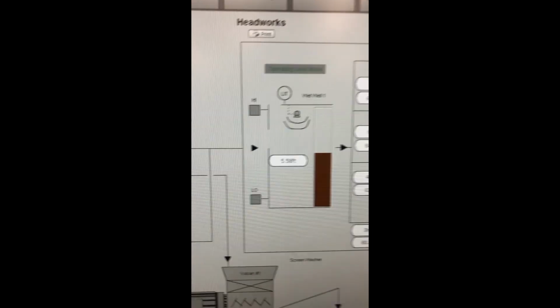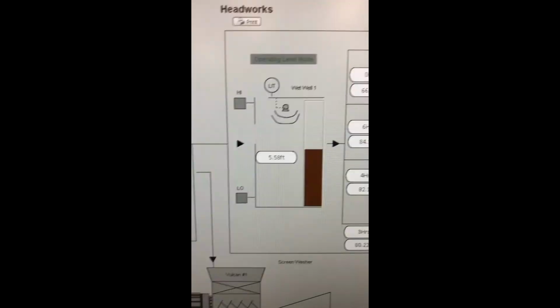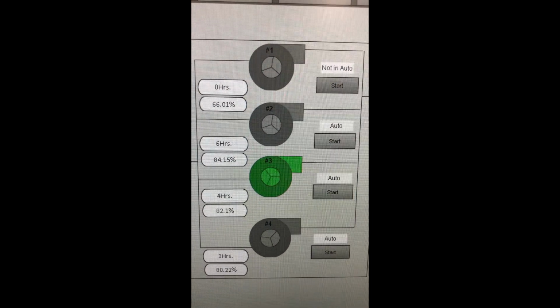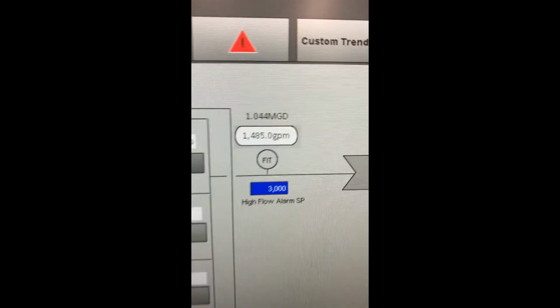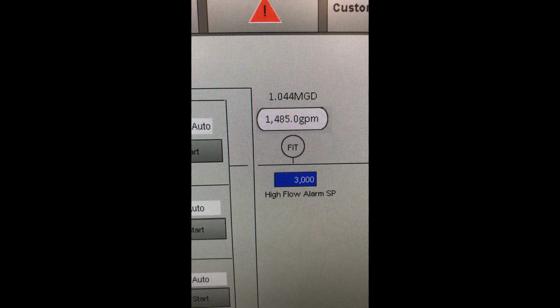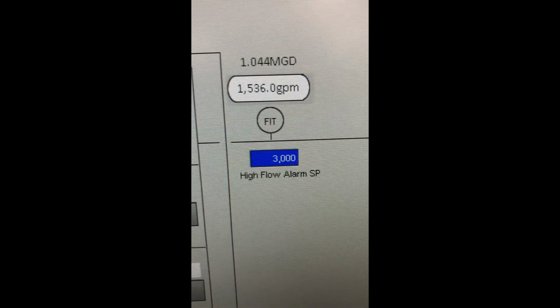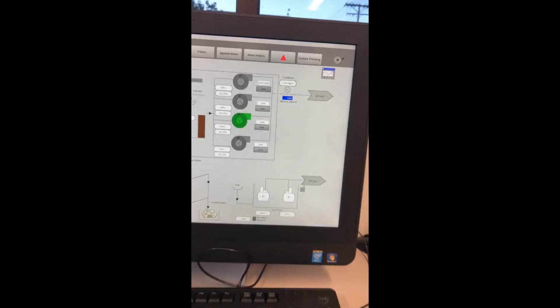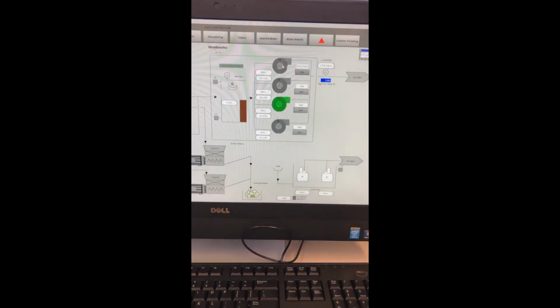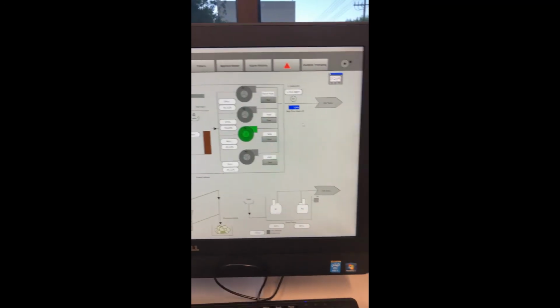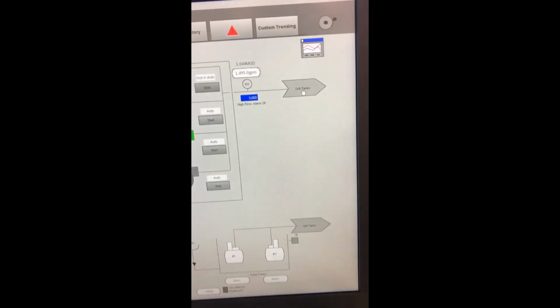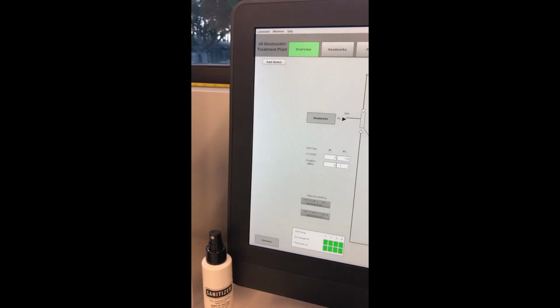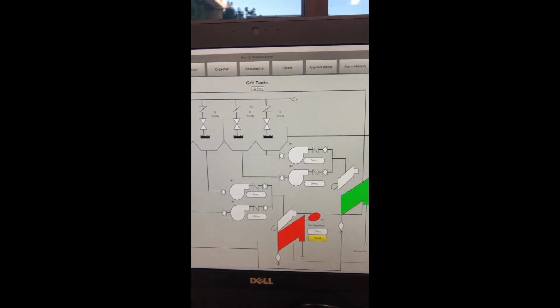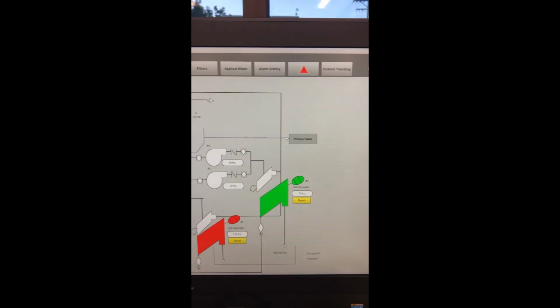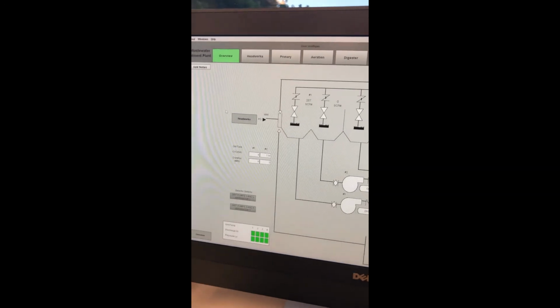We've got our grit pumps, all in kind of a nice graphical format. And here's our influent wet well, okay? Shows you the level in the wet well. And right now the number 3 influent pump or raw sewage pump is running. And currently there's 1,485 gallons per minute coming to the plant, okay? If we click this, it'll take us to the next part of the plant. This is the grit pumps. Go back to here, the headworks.